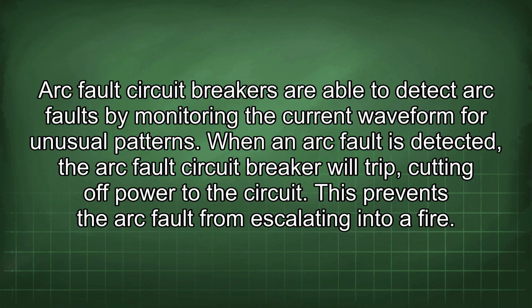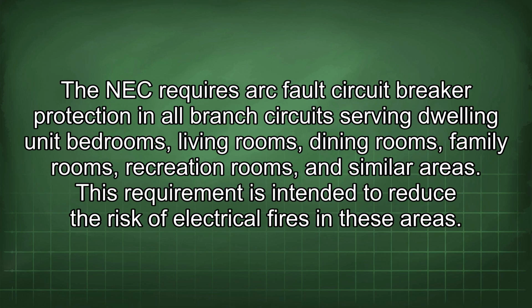This can generate heat and sparks, which can ignite nearby combustible materials. Arc fault circuit breakers are able to detect arc faults by monitoring the current waveform for unusual patterns. When an arc fault is detected, the arc fault circuit breaker will trip, cutting off power to the circuit. This prevents the arc fault from escalating into a fire. The NEC requires arc fault circuit breaker protection in all branch circuits serving dwelling unit bedrooms, living rooms, dining rooms, family rooms, recreation rooms, and similar areas. This requirement is intended to reduce the risk of electrical fires in these areas.